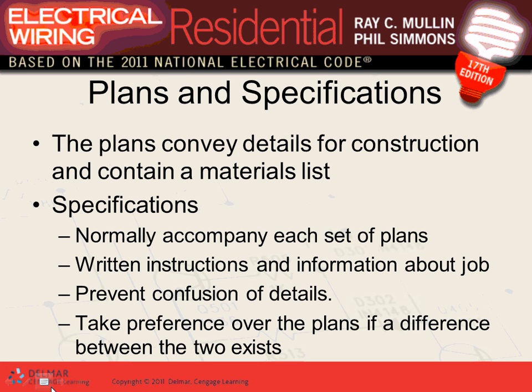To prevent confusion, specifications take preference over the plans. If the specification says you are to use MC cable, and the plan says NM cable is okay, which one rules? The specification. That spec book we send to customers rules over the drawing. So if a drafter screwed up and put a size or something that's not right, your specification, which is typically reviewed a lot by engineers, will take over.